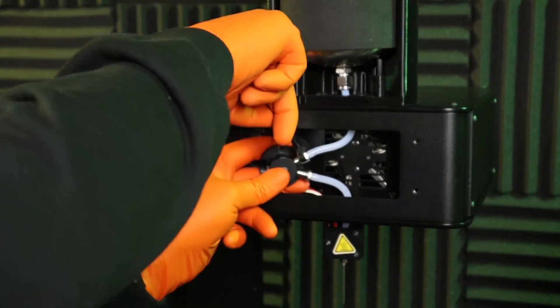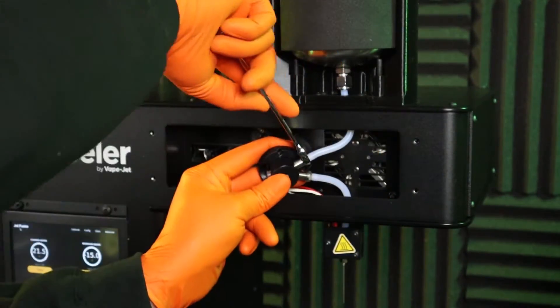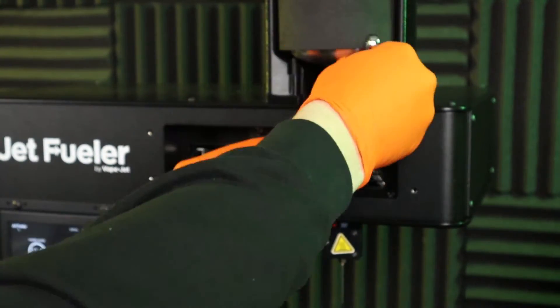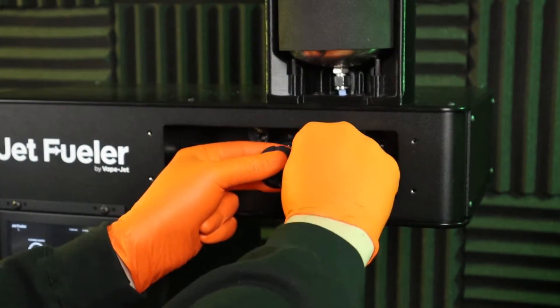Using the 10 millimeter open-ended wrench, loosen the threaded stainless steel barbed adapters and remove both PTFE lines from the valve body. Place the valve body into the beaker with the syringe body, syringe plunger, and 99% isopropyl alcohol.